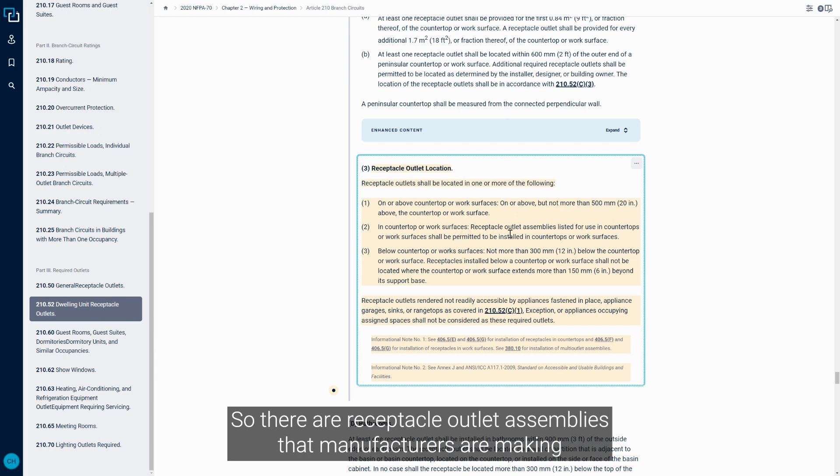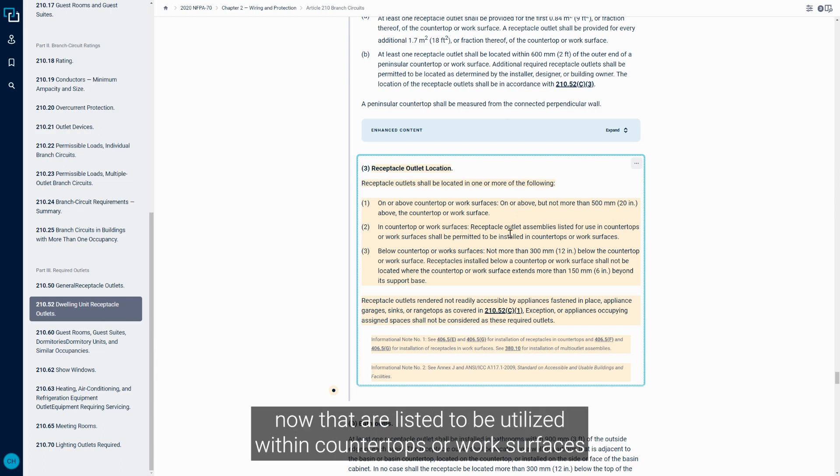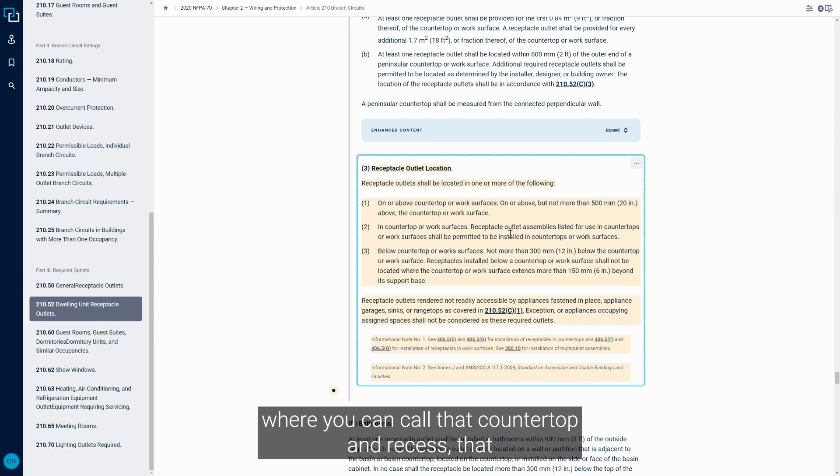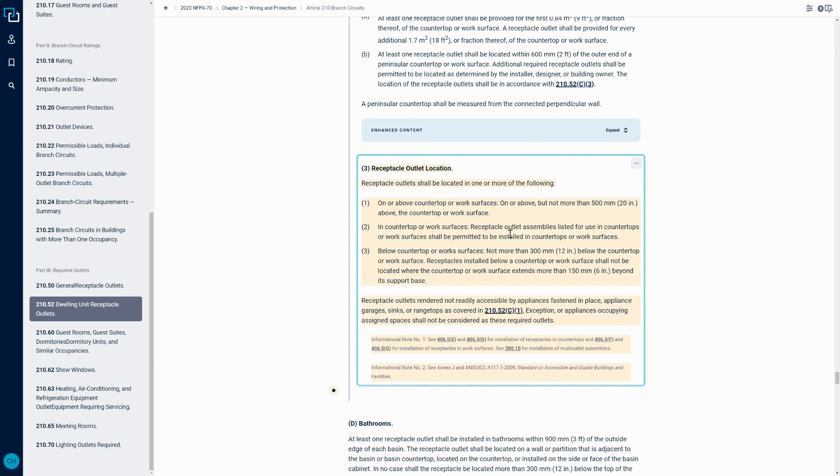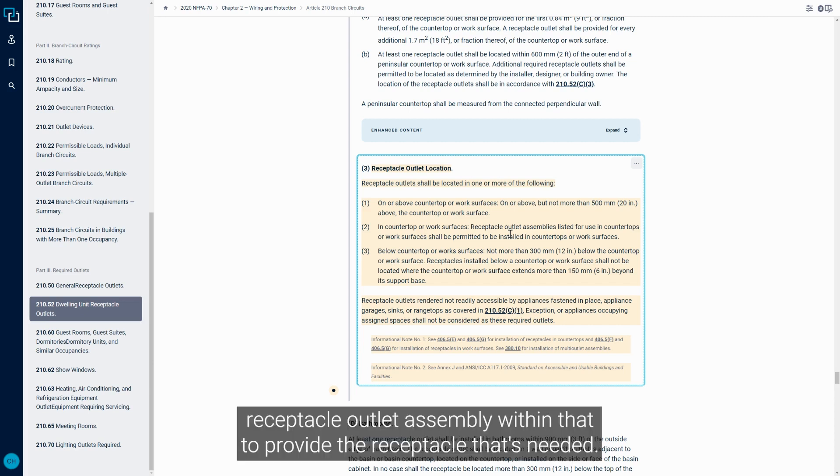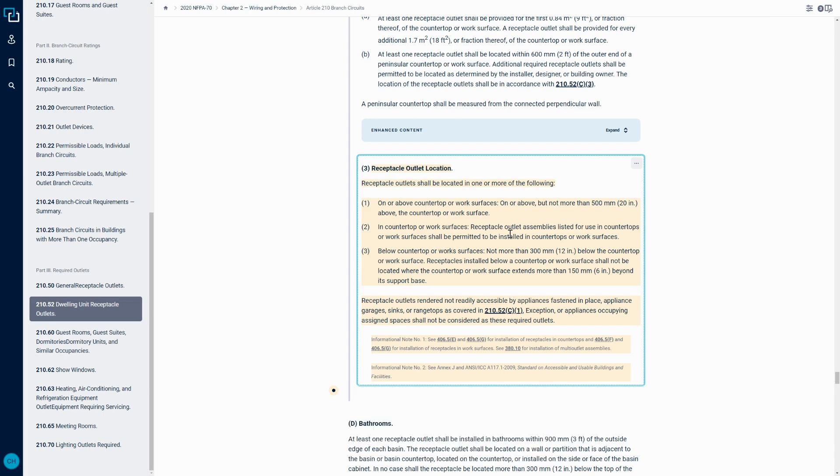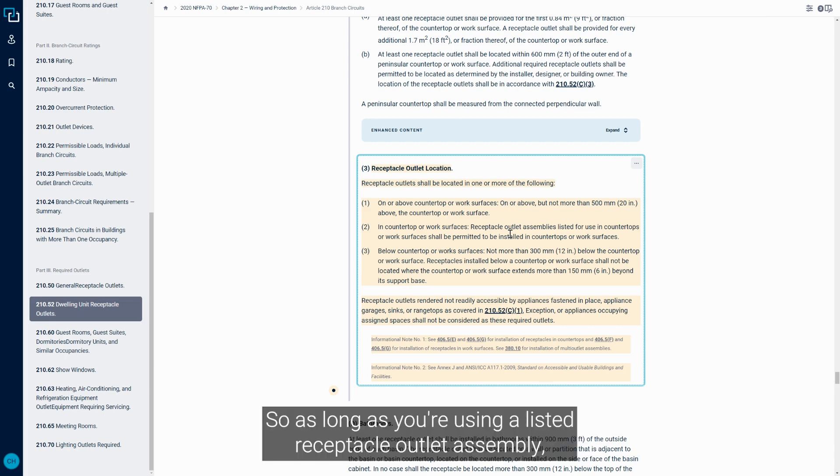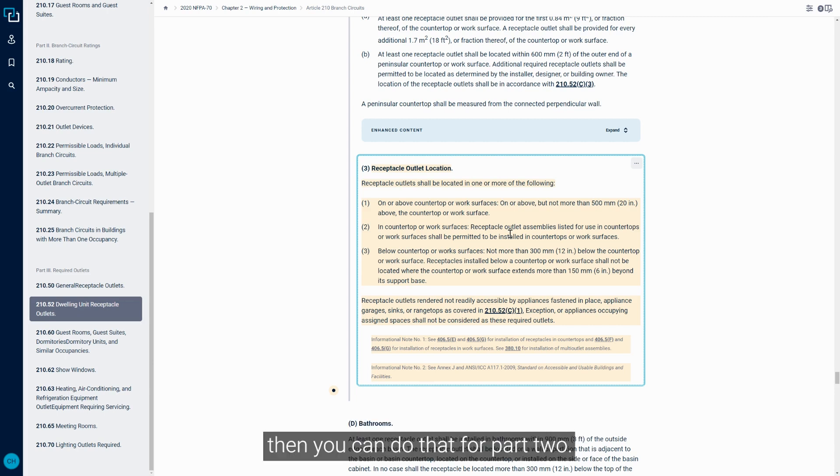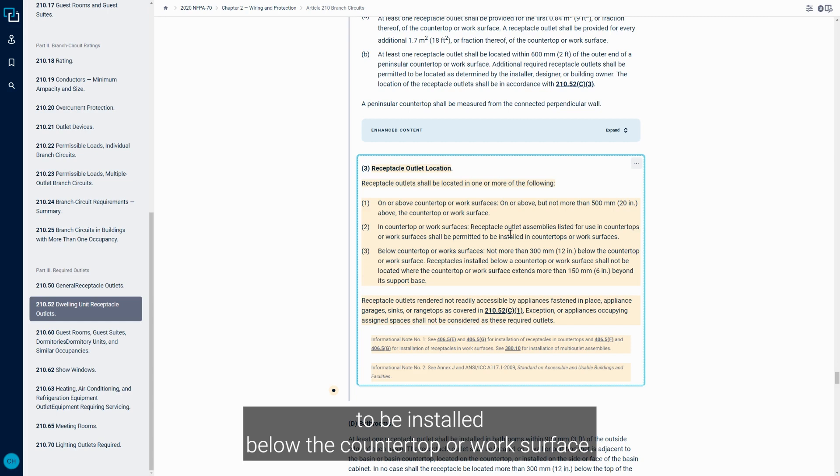So there are receptacle outlet assemblies that manufacturers are making now that are listed to be utilized within countertops or work surfaces, where you can core that countertop and recess that receptacle outlet assembly within that to provide the receptacle that's needed. So as long as you're using a listed receptacle outlet assembly, then you can do that for part two.